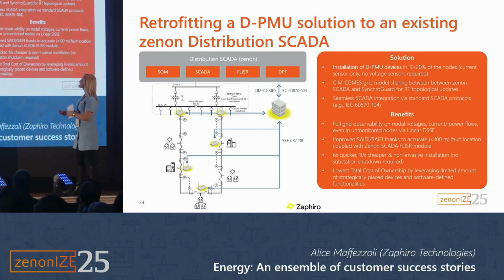In this case, this is the explanation of how we integrate with Zenon. This is an example of an easy retrofit where Zenon is already installed. What we can do is install PMUs in critical points of the grid. The first thing that we do is to receive a single line diagram with the topology. We select critical points of the grid. We install PMUs in the primary and in critical points of the secondary substations, and then we integrate with the SCADA.